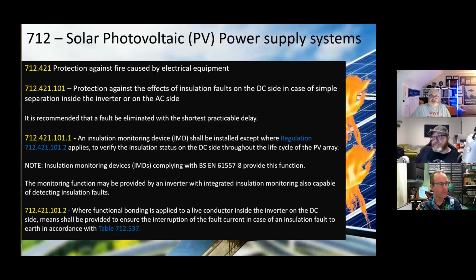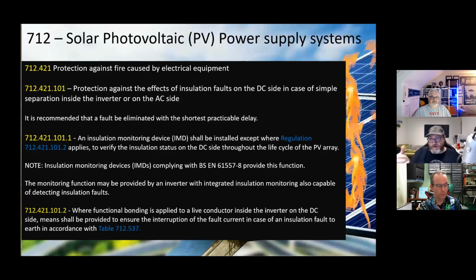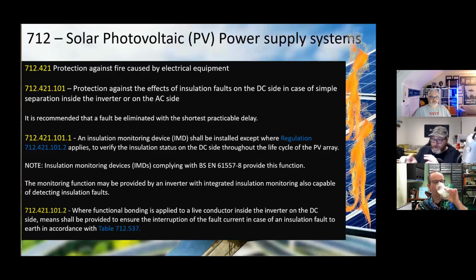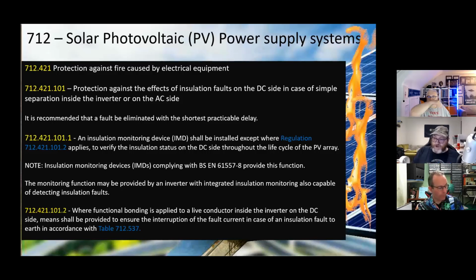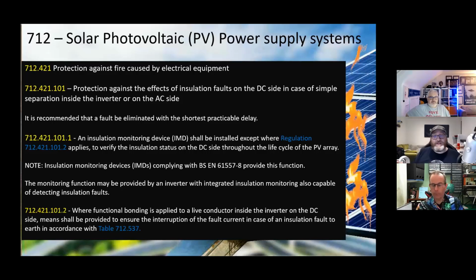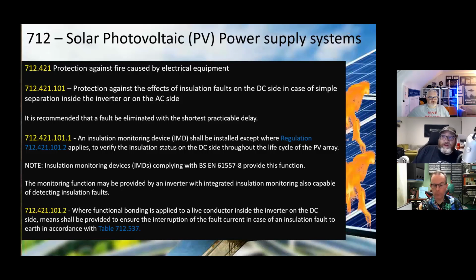The PV array. And this is an important decision to make at the point of design. You've got to consider the life cycle of the equipment. This is something we did cover in this asset management webinar. And IMDs are there to do that. They will constantly carry out tests, and they'll give you the first hint of insulation degradation. The monitoring function may be provided by an inverter with integrated insulation monitoring, also capable of detecting insulation faults.